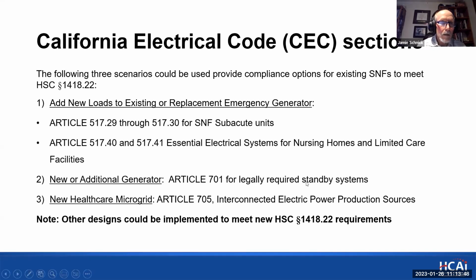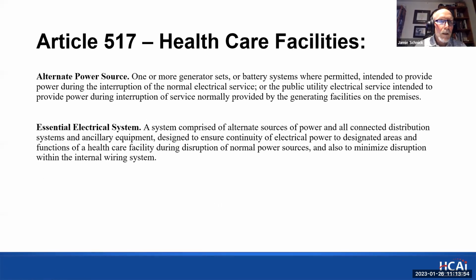So again, I'll step through these, but here's a brief summary of the 3 options. On the 517 solution, I think it's relevant to point out that 517 has definitions that identify alternate power source: 1 or more generators or battery systems permitted, intended to provide power during an interruption of the normal electrical service. And essential electrical system: a system comprised of alternate sources of power and all connected distribution systems and ancillary equipment. The reason I include these is just to make the distinction that there's the power source and there's the distribution system that are required by the 517 for the essential branch.